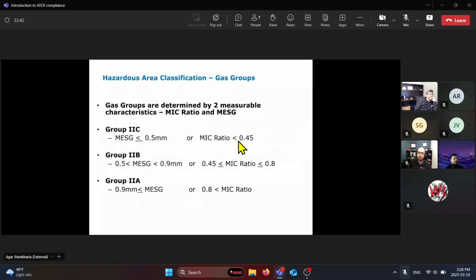And then I think you were asking regarding the gas concentrations, I would say. So these are some of the concentrations that they describe in the standards. Again, if you look up the standards, you would be able to see there are different tables in the standard, depending again on the method of protection. And most of these would only apply to explosion-proof testing, for us to have that environment created with that much ignitable gas.